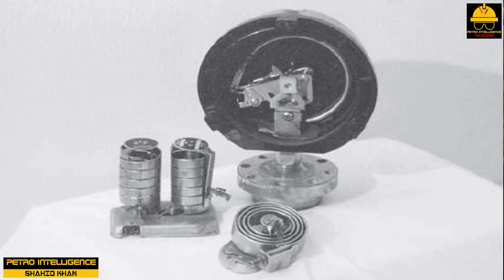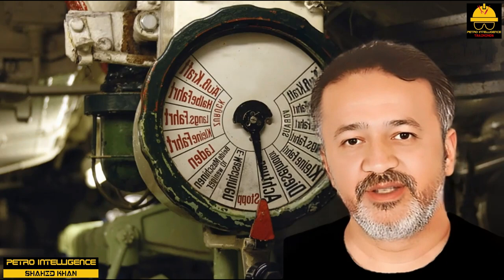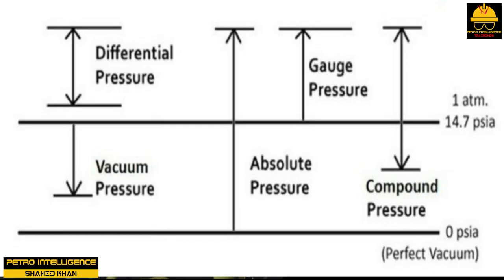These pressure changes can affect product quality, so many pressure elements have been invented to monitor and control pressure. There are three commonly used pressure scales in the manufacturing environment: gauge, absolute, and vacuum. The most commonly used is the gauge scale, where values are expressed in pounds per square inch gauge (PSIG); the gauge scale starts with atmospheric pressure (14.7 PSI) as zero. The absolute pressure scale starts with a perfect vacuum as zero; values are expressed in PSIA. To convert from gauge to absolute pressure, add 14.7 to the PSIG value.